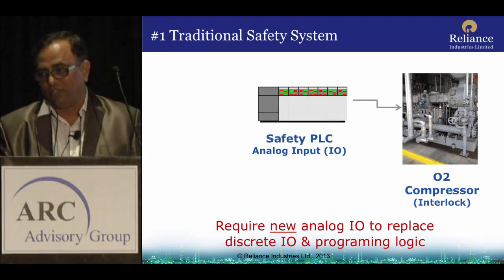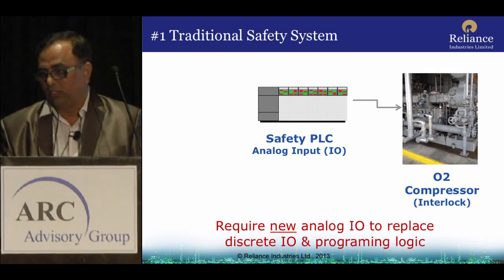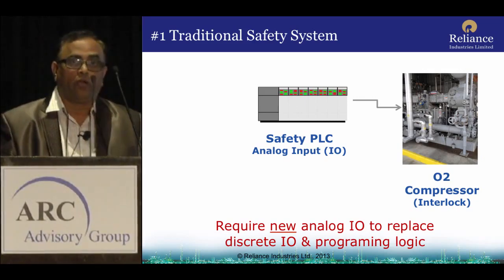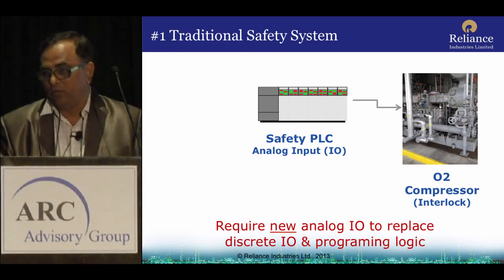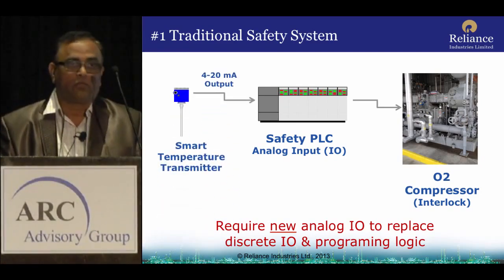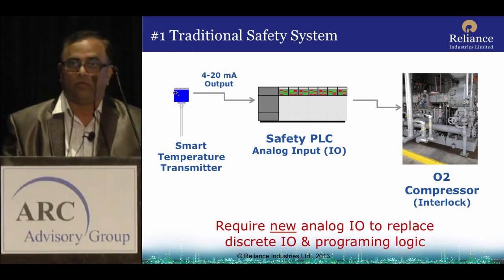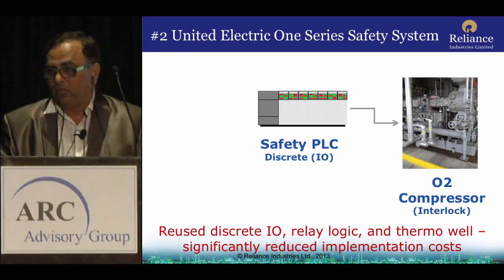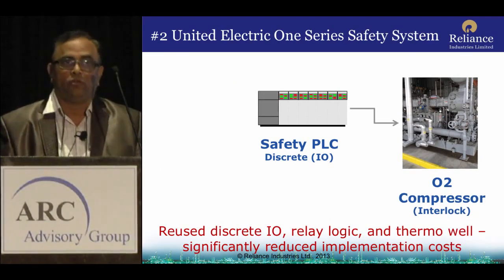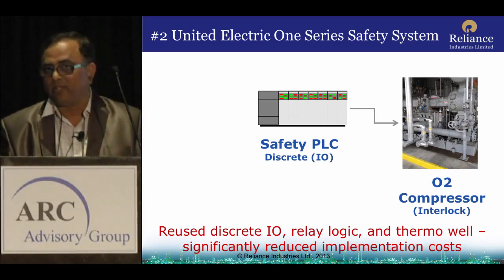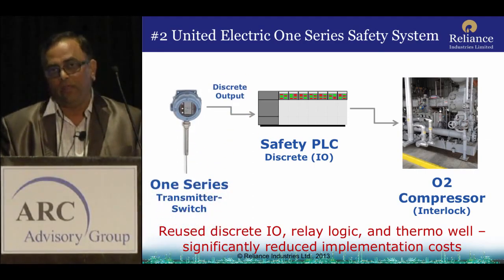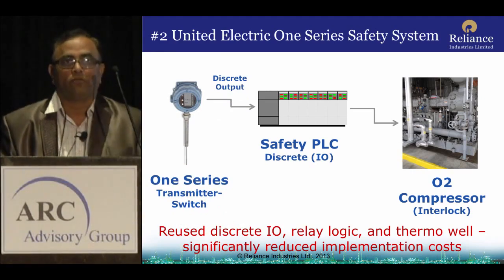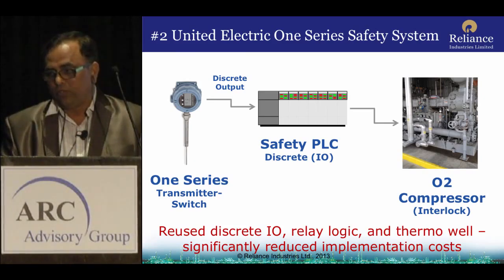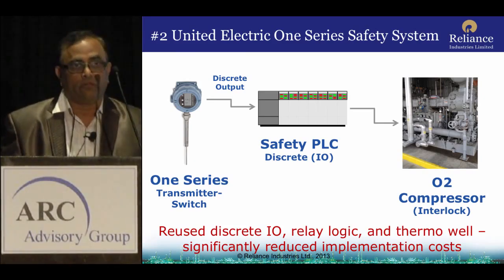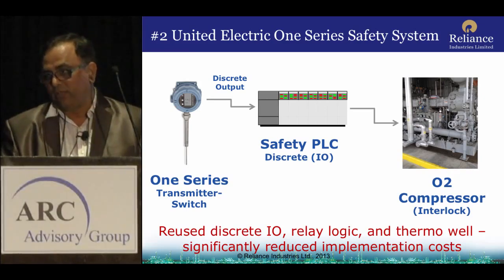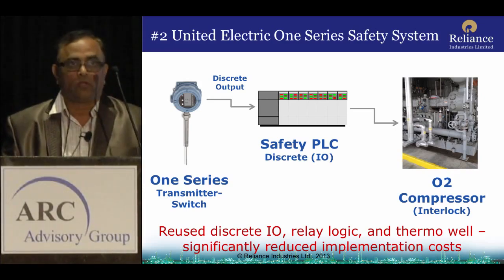The traditional safety system has analog input safety PLCs, which require new analog IOs if you want to replace them. So, it is the traditional thing: the temperature transmitter connected to your logic solver with the analog input. Now, with this switch, there is no change of the logic solvers or any setup in the running system; you only remove the electromechanical switch and put in the smart device. Reuse discrete IO and relay logic, including the field thermowell, which significantly reduces the total overall cost.